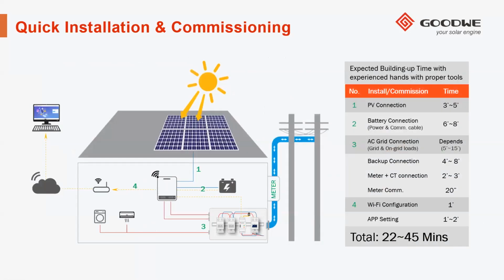So the installation and commissioning of our inverters are actually quite quick, especially once you've got used to the setup of the system. It's normally between 22 and 45 minutes. With your PV connections, 3 to 5 minutes, battery connection, 6 to 8 minutes. AC grid connection is all dependent on how far your DB board and everything is from your inverters. And the Wi-Fi configuration and app settings normally takes a few minutes.